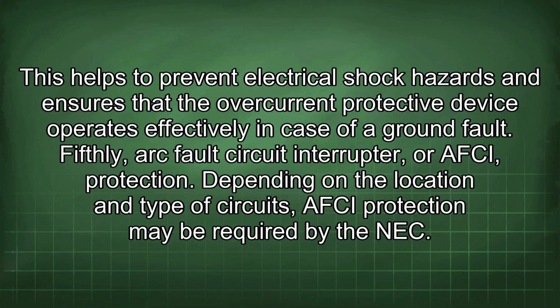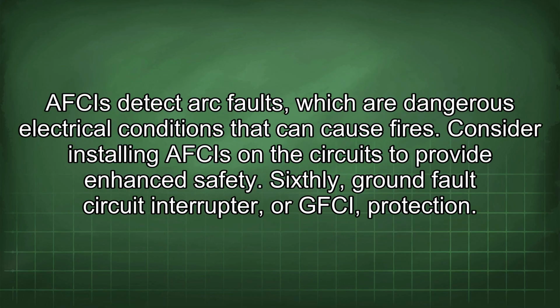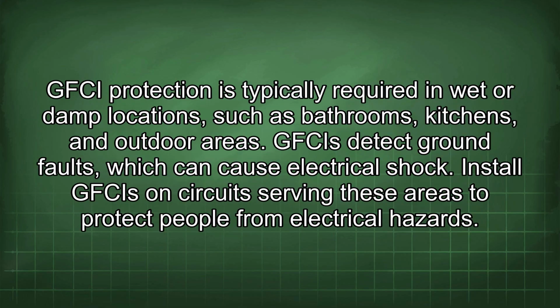Fifthly, arc fault circuit interrupter, or AFCI, protection. Depending on the location and type of circuits, AFCI protection may be required by the NEC. AFCIs detect arc faults, which are dangerous electrical conditions that can cause fires. Consider installing AFCIs on the circuits to provide enhanced safety. Sixthly, ground fault circuit interrupter, or GFCI, protection. GFCI protection is typically required in wet or damp locations such as bathrooms, kitchens, and outdoor areas. GFCIs detect ground faults which can cause electrical shock. Install GFCIs on circuits serving these areas to protect people from electrical hazards.